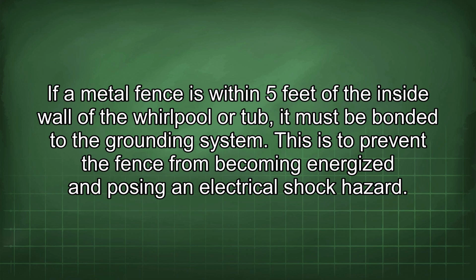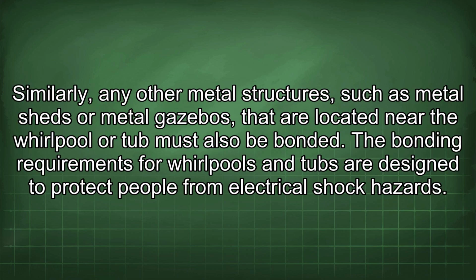If a metal fence is within 5 feet of the inside wall of the whirlpool or tub, it must be bonded to the grounding system. This is to prevent the fence from becoming energized and posing an electrical shock hazard. Similarly, any other metal structures, such as metal sheds or metal gazebos, that are located near the whirlpool or tub must also be bonded. The bonding requirements for whirlpools and tubs are designed to protect people from electrical shock hazards.